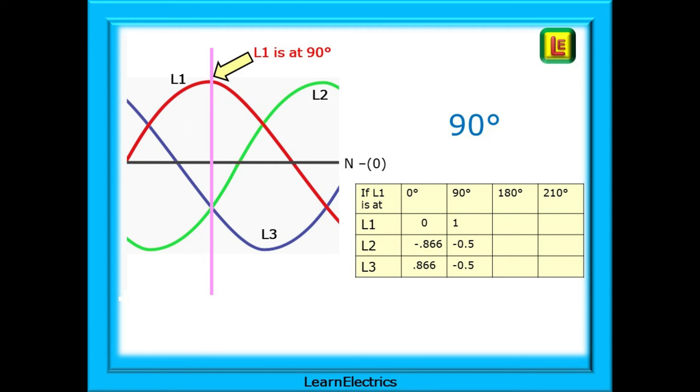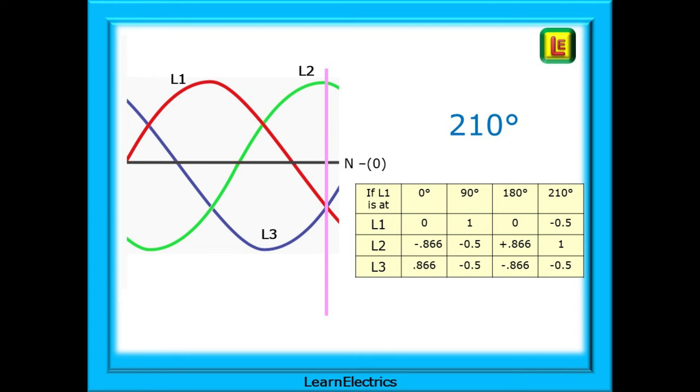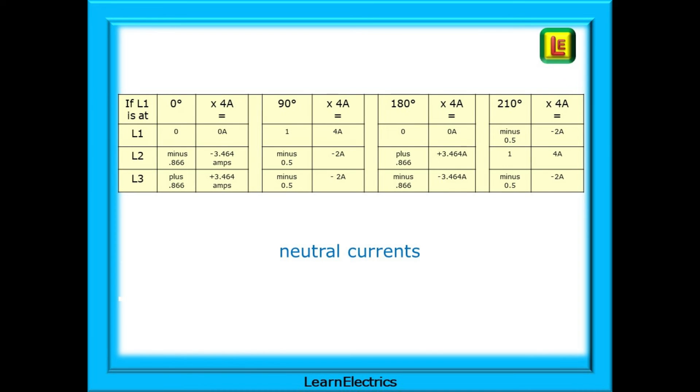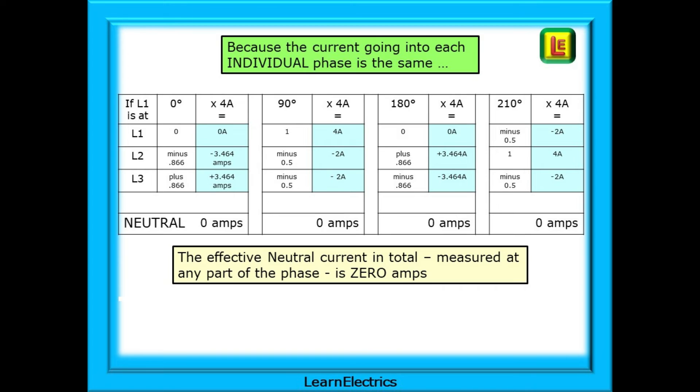Moving on a little bit, a few fractions of a second later, the lilac bar is at 90 degrees for L1 and L1 is at a maximum, a value of 100% or plus 1. The green and blue are both negative and are sat at minus times 0.5 for each. And these numbers can also be entered into the grid. At 180 degrees, things have changed again. And at 210 degrees, a different picture again. And we've completed the grid numbering for you. Shown here is a completed table to give you an idea of what is going on. As we are using the same 4 amp heaters, the multiplication factors have been applied to the 4 amp neutral currents already. If we take that table and add up all the neutral currents, what do we get?